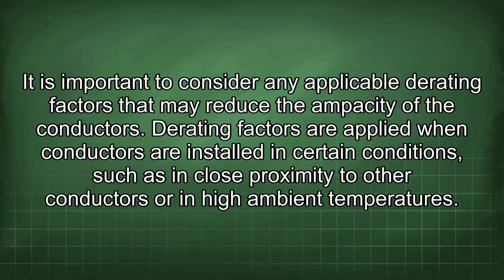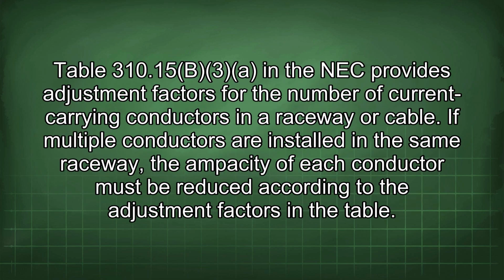It is important to consider any applicable derating factors that may reduce the ampacity of the conductors. Derating factors are applied when conductors are installed in certain conditions, such as in close proximity to other conductors or in high ambient temperatures. Table 310.15(B)(3)(a) in the NEC provides adjustment factors for the number of current-carrying conductors in a raceway or cable.